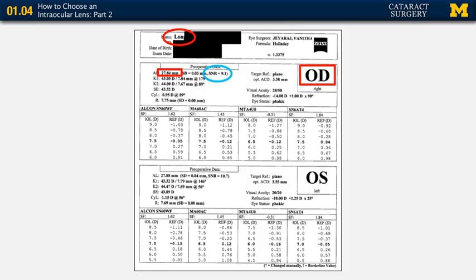Our next step here is testing the quality of the study. So we have an IOL Master. We want to look at the signal-to-noise ratio. We'll talk a bit more about this when we come to the second sheet of this handout, because that's where we get a bit more information as far as the waveform and also a spread of signal-to-noise ratio. But here we have a fairly reliable study, as we can then see with looking at symmetry between the 2 eyes. We have the right eye and the left eye, and we see both fall at about 27.8, so symmetry check is done as well.